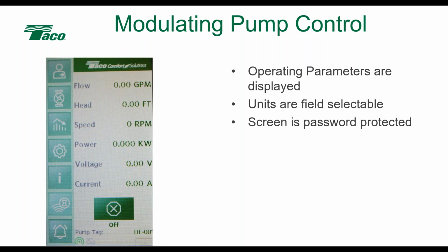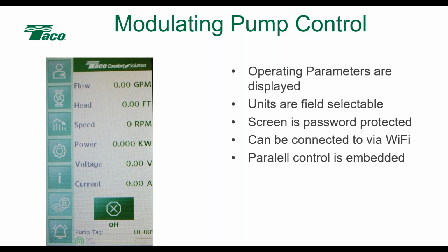The screen is password protected, so not anybody can just walk up to it and touch it and do anything to it. You can also connect to it via Wi-Fi, which is kind of nice for setup, which is the preferred method of setting it up, is to go through the Wi-Fi interface, which I'll show you another screen here in just a minute. And the nice part is that parallel control that I just got done talking about is embedded in this controller. So it doesn't take anything in the way of the BAS to write any fancy sequencing. All they have to do is send the pumps a start-stop signal. And these can all be connected back to the BAS via BACnet or Modbus. So they've got flexibility. They can read everything that's going on, but they don't have to do anything other than tell it it's time to run.